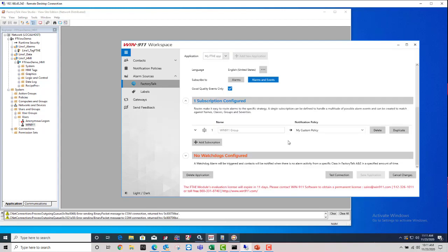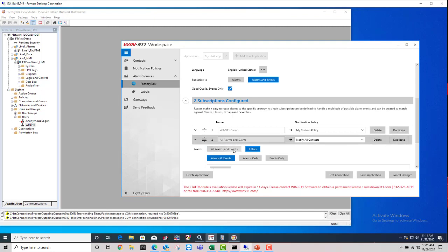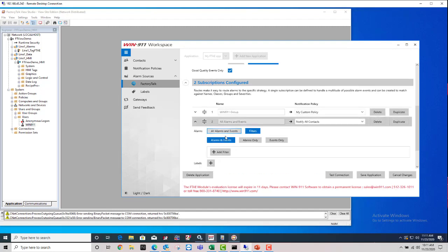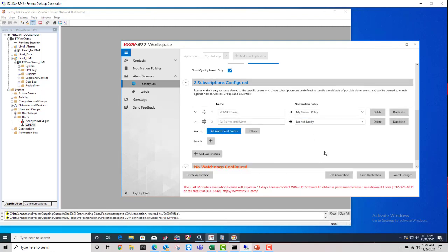Now, one thing I would recommend, especially for the initial setup, you don't have to keep this around long-term, but especially in the beginning, add another subscription for all alarm and events. Just keep that button selected. Don't go into the filters, just all alarm and events. And you can send that to a do not notify.